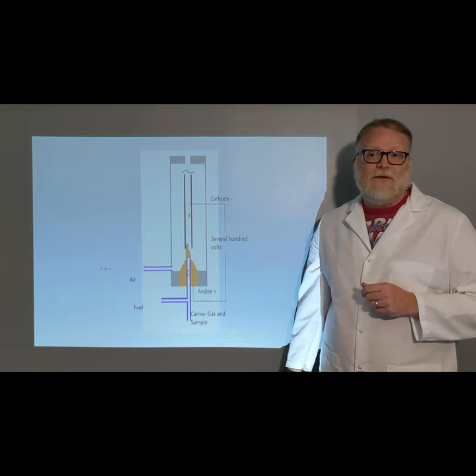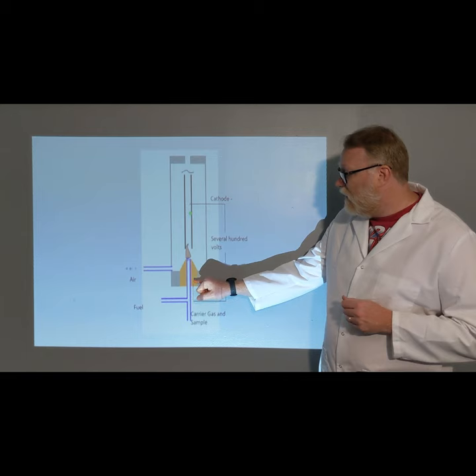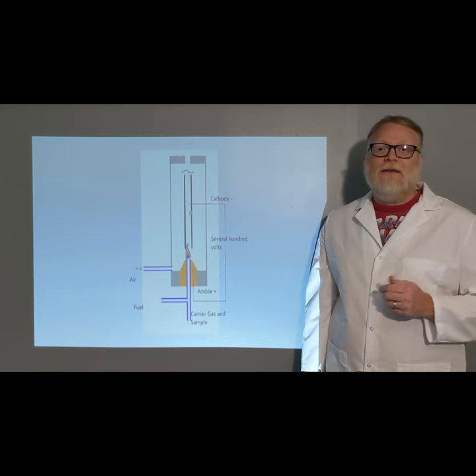If your column is too far into the jet, it could heat up, resulting in your stationary phase being baked off, giving you some unwanted results.